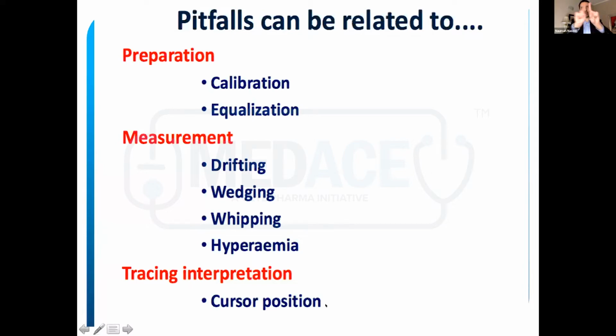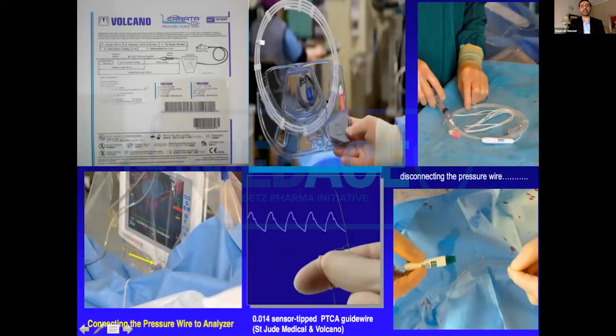And when you have the cursor on the FFR tracing, some machines have the option that you can run it across. Make sure the cursor is at the position where the tracing was appropriate and there was no artifact. So this is what the FFR wire looks like when it comes in the packet. The key thing is that once you have the coil, wire packet down and you flush it, leave it there for a good 60 seconds before you hook up the wire with a transducer and press the 0 button, because otherwise you may not calibrate properly. And the wire is like any other 0.014 wire, just not as torqueable.